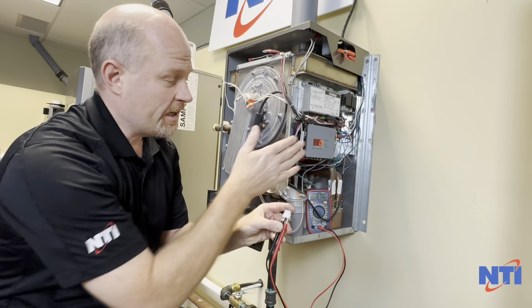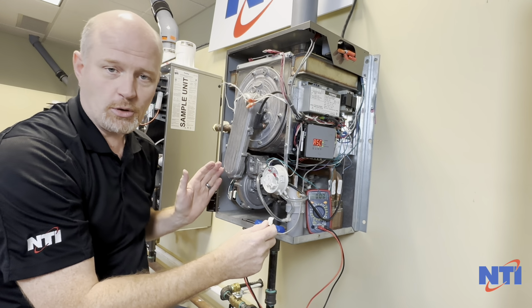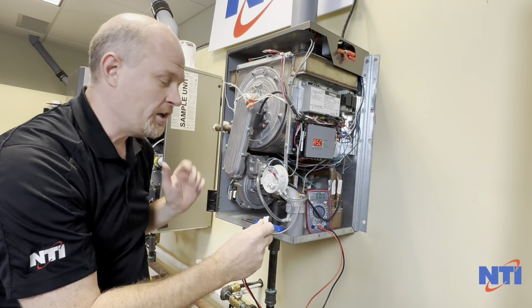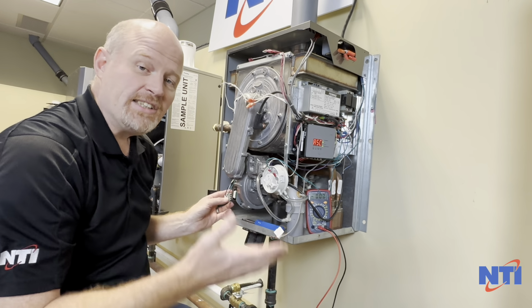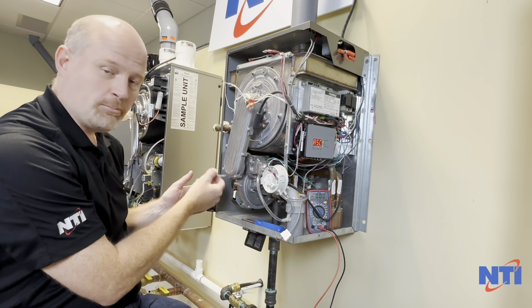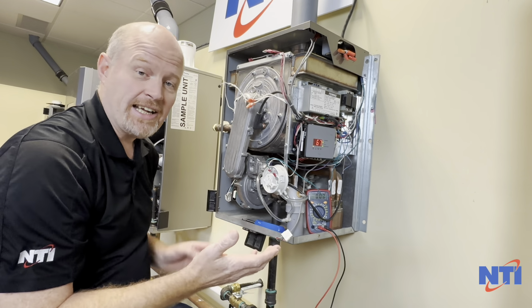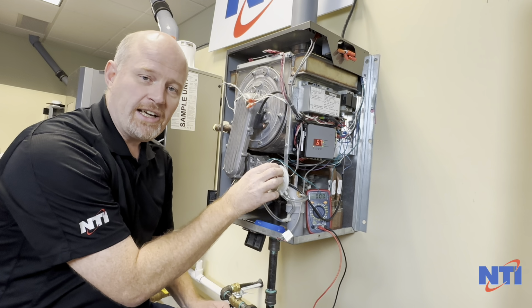In this case, we've diagnosed the Sentry control is actually working fine, and for some reason our combustion blower fan is failing to turn off. At that point, you need a new fan. Now, if your blower is turned off completely, so it's just not running, maybe you've unplugged the low voltage and you're still getting an ASC code, that would indicate that something is holding the air switch closed.